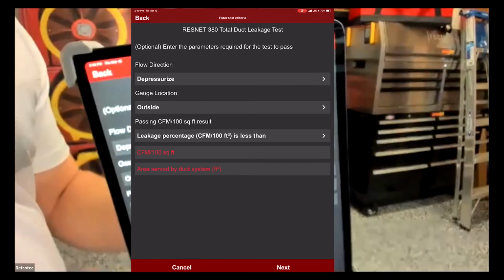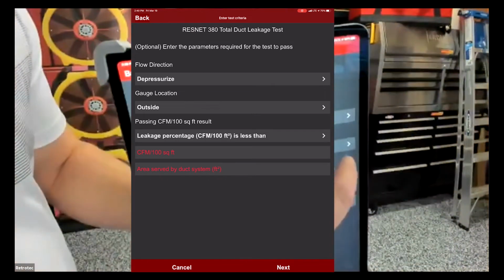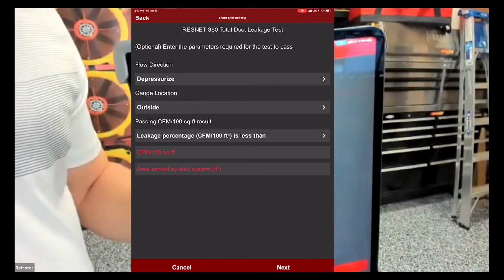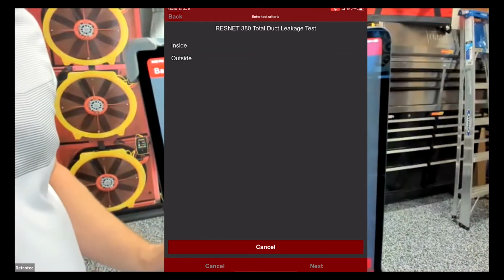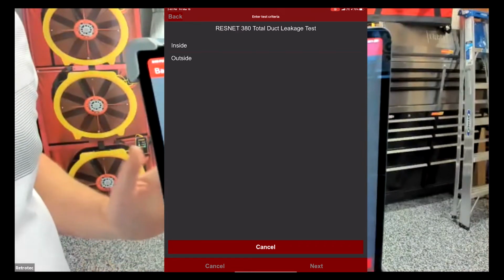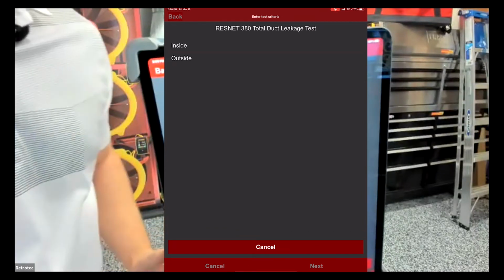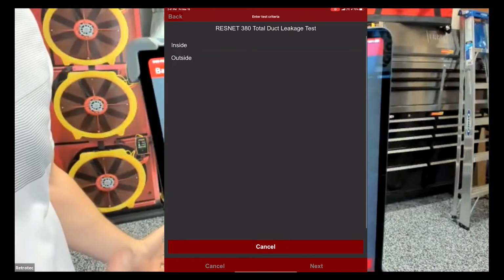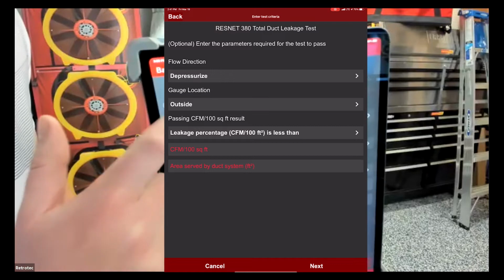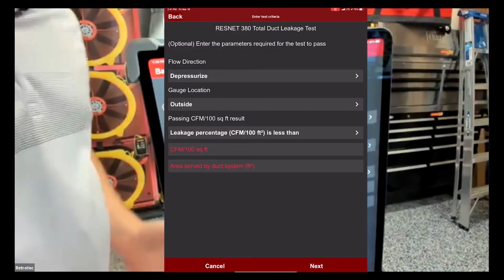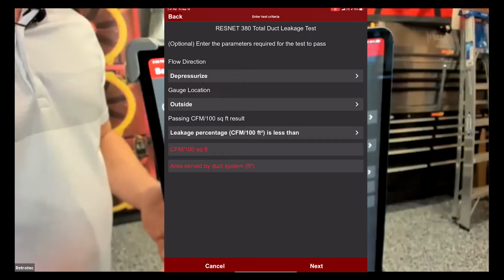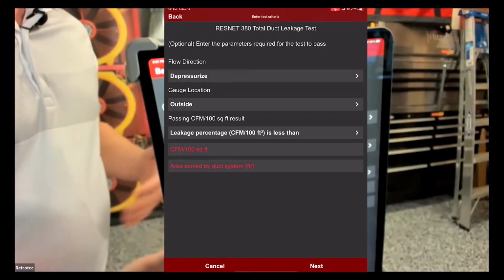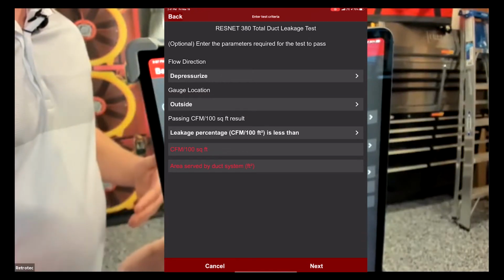Okay, so this gauge location, you have the option of saying outside or inside. This does not mean inside or outside of the house. And I know this is going to sound a little wacky, but the software has to have this input. What this means is, is the gauge inside or outside of the duct system? That's always going to be outside of the duct system. We don't test with the gauge inside. You really can't do that. The reason we have to have this in is for the app to be able to allow the test to go in either direction.